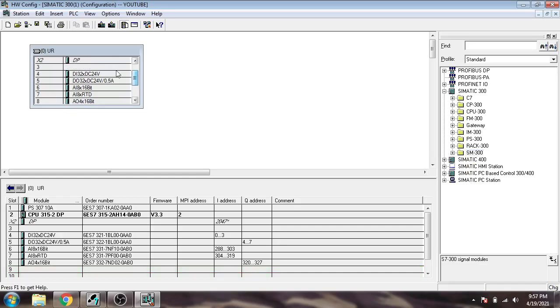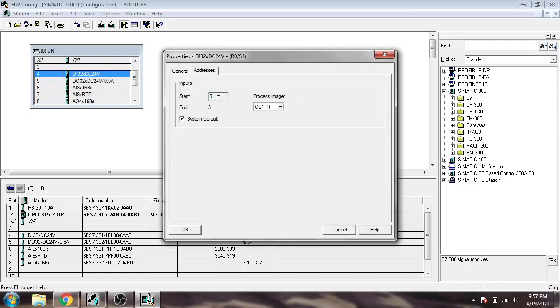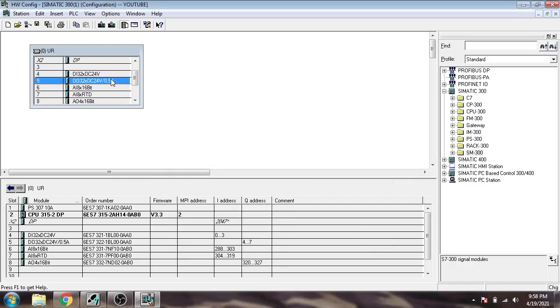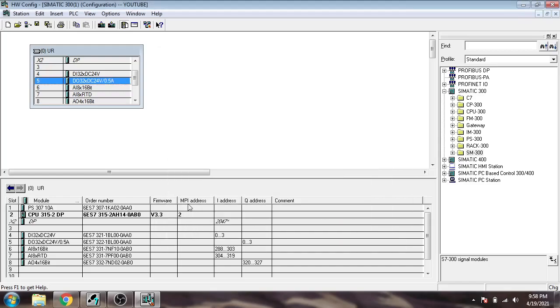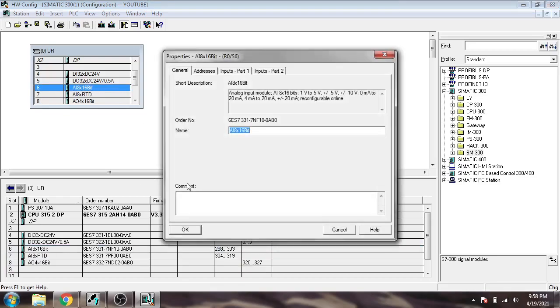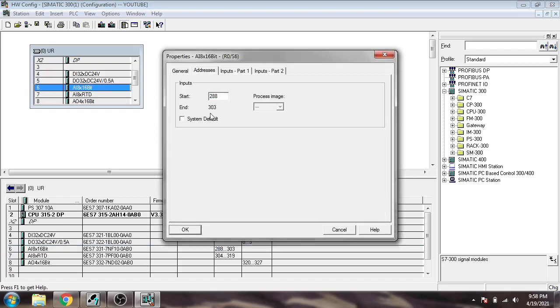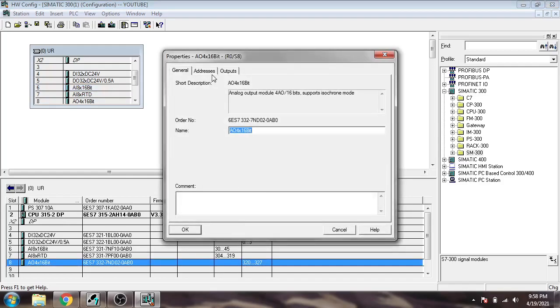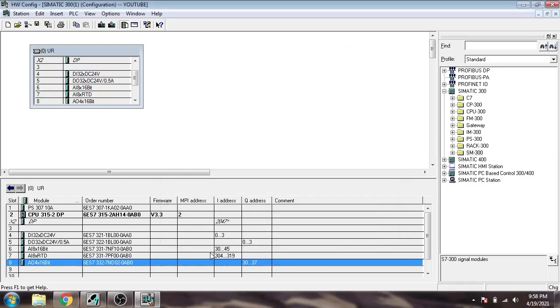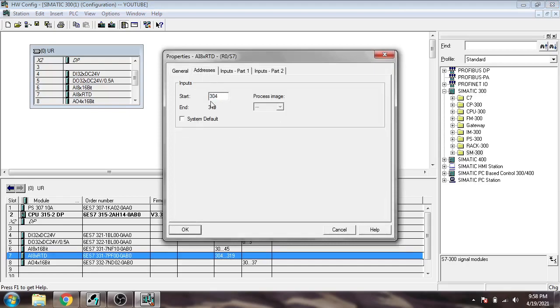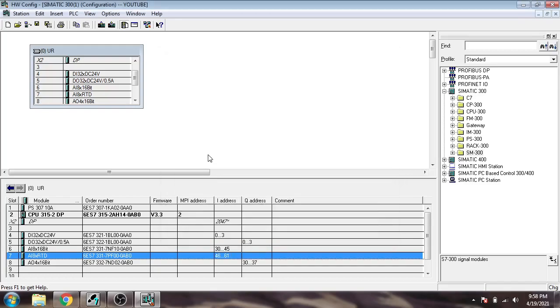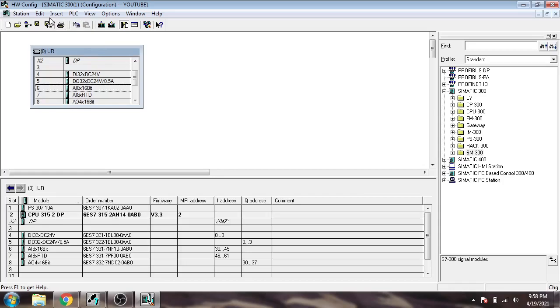Now we're going to configure addresses. You'll see here is an address, it starts from 0 to 3. If I change that to 0 to 7, you'll see it changes. Now I'm choosing analog input addressing to 30. Analog output, we're also using from 30. You'll see how we change our address. Now I'm going to choose that to 0 to 6. You'll see our PLC modules have now been added.